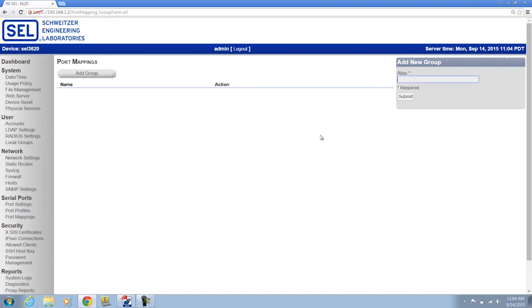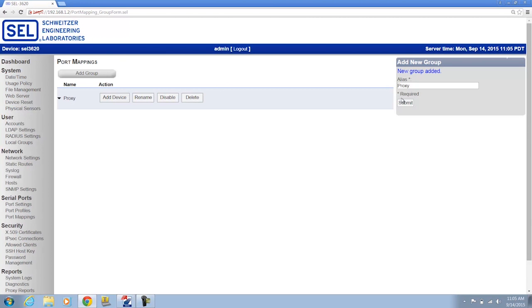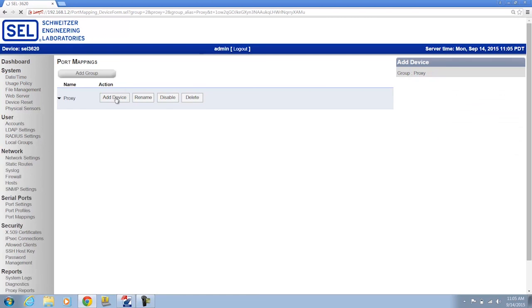Now, this group is going to allow me to instantiate an Ethernet Listen Local driver using Secure Shell, and this will allow me to access the relay through the SEL3620. So I'm going to call this new group Proxy, and then my next step is going to be to add an Ethernet Listen Local driver that will allow me to access the relay.